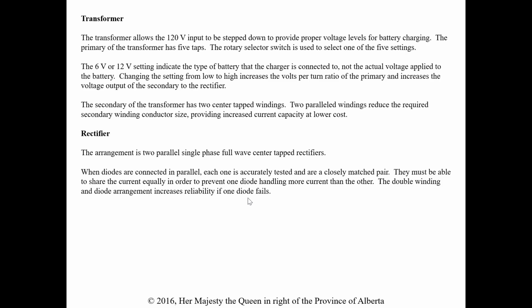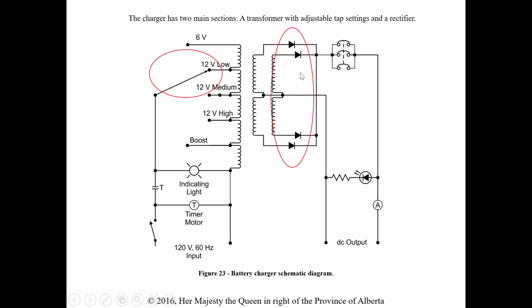The secondary of the transformer has 2 center tap windings. Two parallel windings reduce the required secondary winding conductor size, providing increased current capacity at a lower cost. So in this transformer section, paralleling these two windings gives us twice the current because each only has to be rated for half of it.